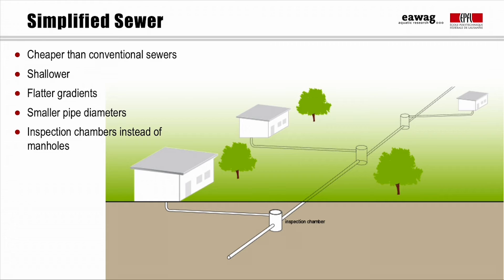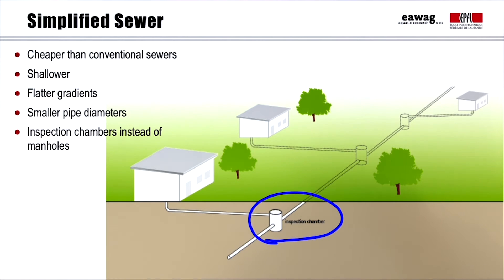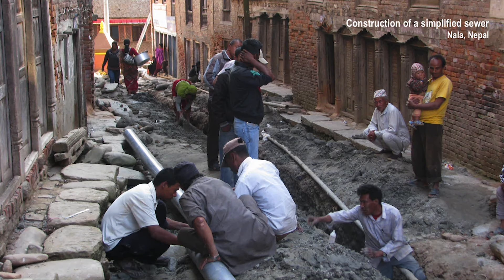Some of the main differences with conventional sewers are the minimum depth, which is about 30 cm instead of 80 cm; the minimum gradient, which is about 0.5% instead of 1%; and the minimum diameter of the pipes, which is about 100 mm instead of 200 to 300 mm. Another important difference is that expensive manholes are unnecessary — instead, simple inspection chambers or clean-outs are sufficient, and inspection boxes are built for each house connection. The drawback of the lower gradient and diameter is that repairs and removal of blockages are more frequent, but this can be done easily by locals at little cost.